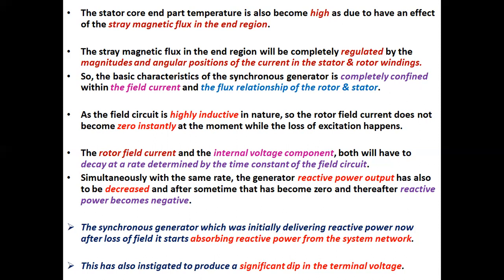Simultaneously, with the same rate, the generator reactive power output has also to be decreased, and after some time it becomes zero, and thereafter reactive power becomes negative. The synchronous generator which was initially delivering reactive power now, after loss of field, starts absorbing reactive power from the system network. This has also instigated a significant dip in the terminal voltage.